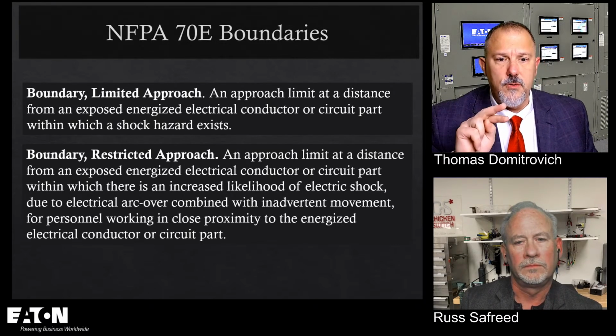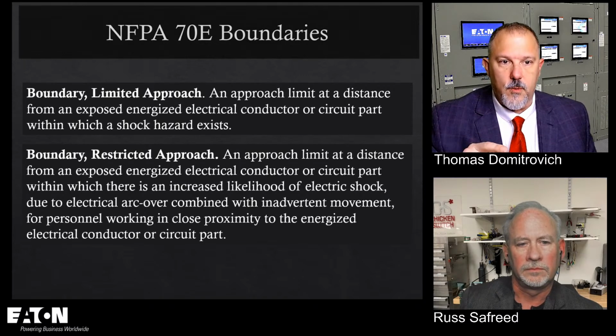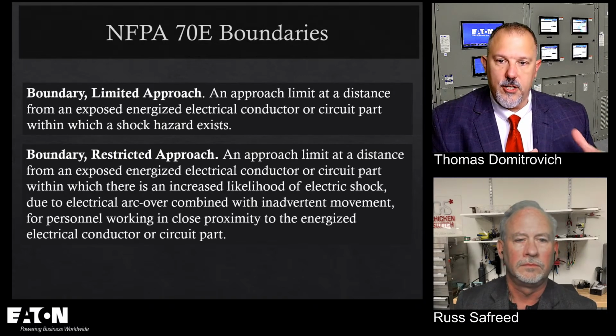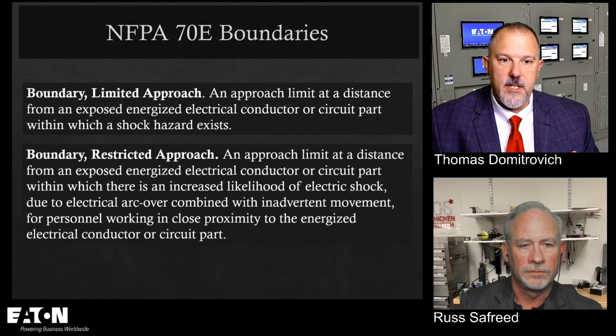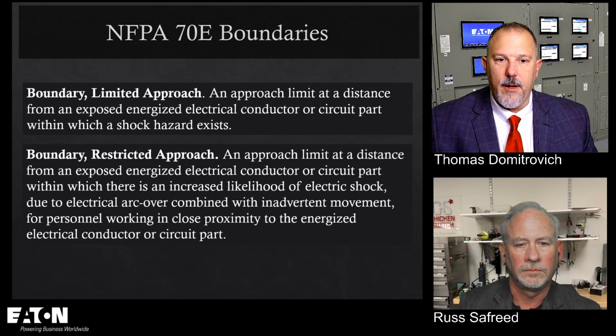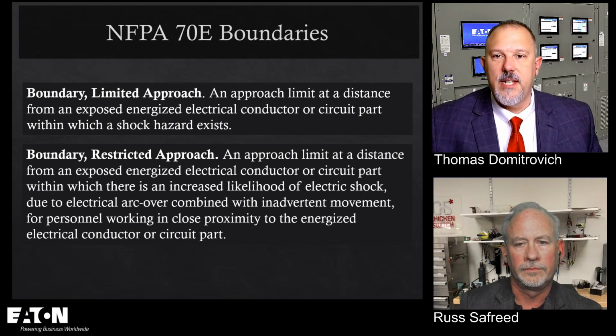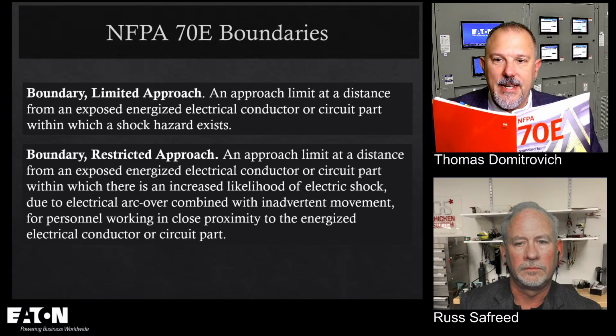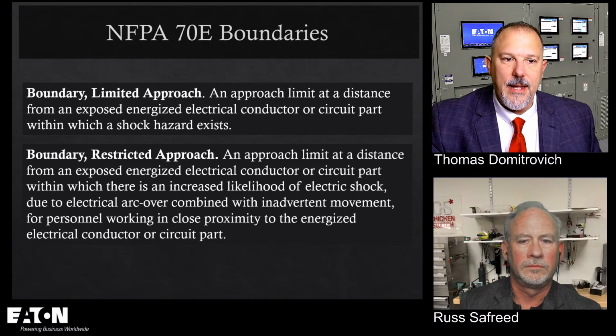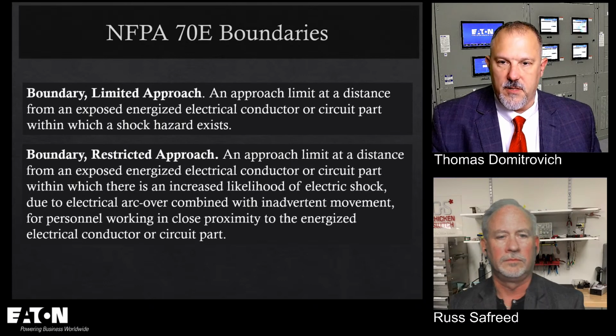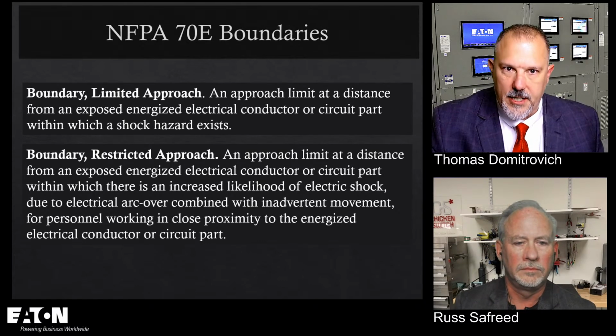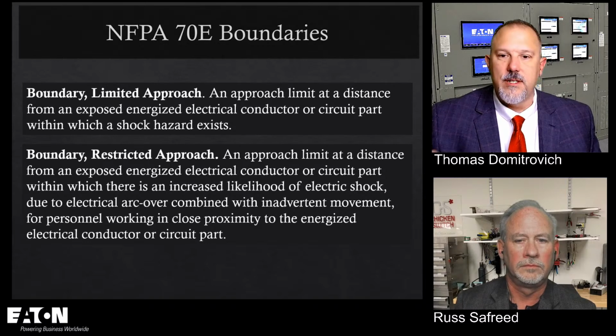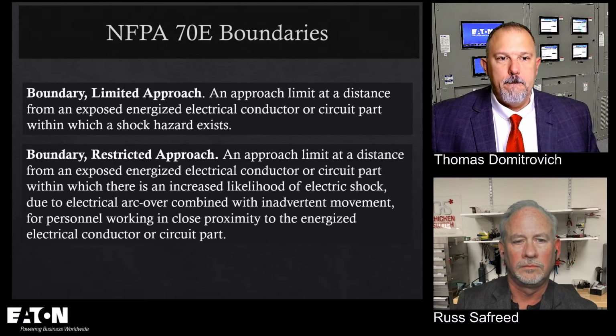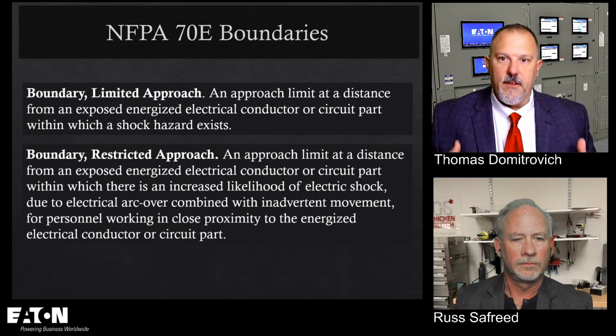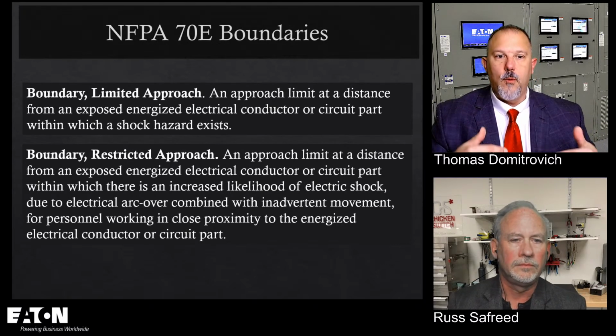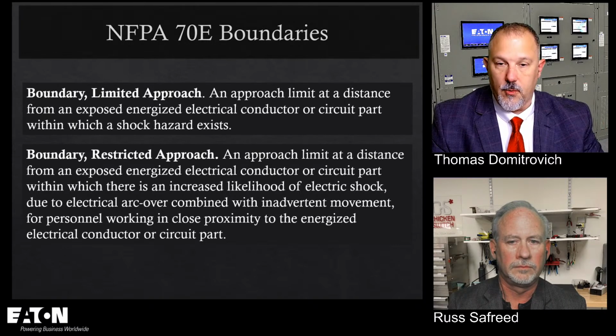These two boundaries are focused on shock. The first one is relatively close to the exposed conductors, and the second one is a little further away. 70E tells you who can be within each of these boundaries, what training level and qualifications are needed, and how you treat individuals within them. So what we're talking about here is getting outside the arc flash boundary, not necessarily what you're doing with regard to the restricted approach or limited approach boundaries.